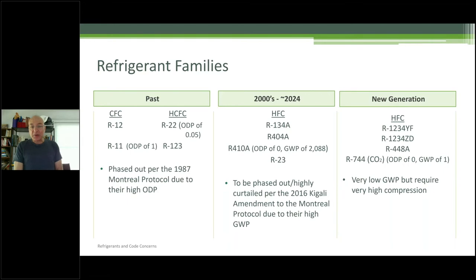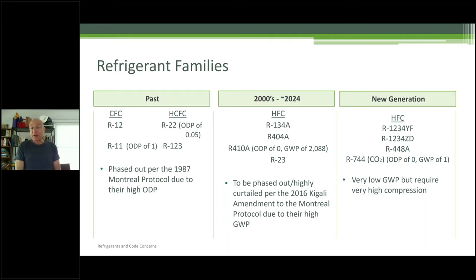In 2024, the Biden administration is trying to speed up the phase-out of 410A, which is what we mostly use today in VRFs. The problem is that the CFCs and HCFCs depleted the ozone layer. The ozone-depleting potential of R22 is 0.05, while 410A is zero — fortunately. However, the global warming potential of 410A is 2,088, meaning one pound of 410A going into the atmosphere has the effect of 2,088 pounds of CO2 being discharged. That's enormous.